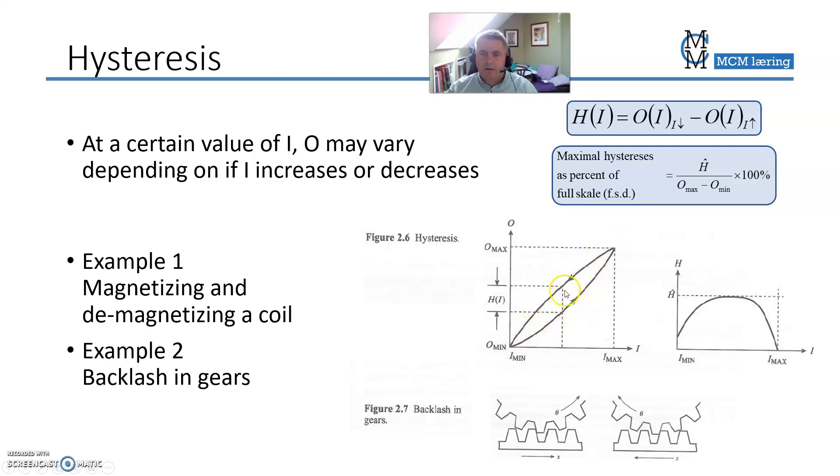The hysteresis is often given as a percent of full-scale deflection. So you look at it with respect to the output span and then you make it into percent.